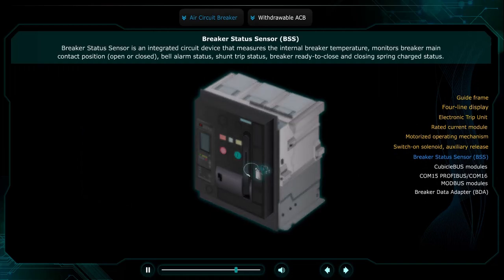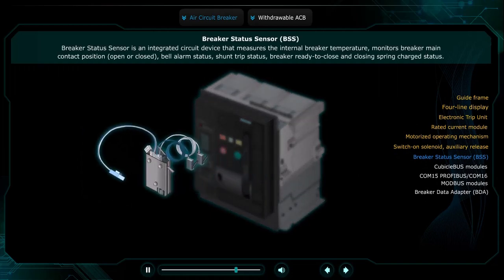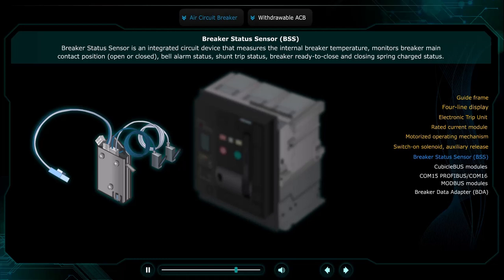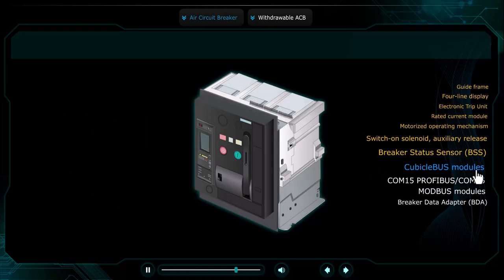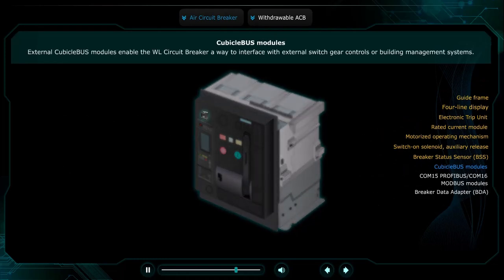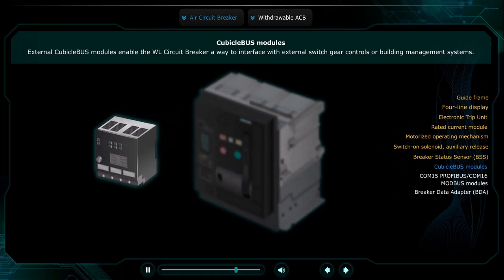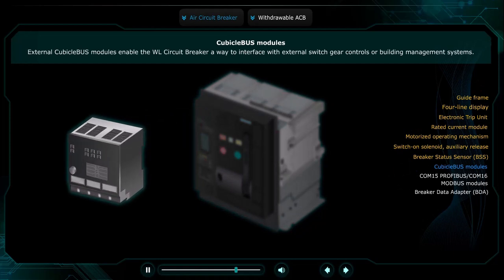Breaker status sensor is an integrated circuit device that measures the internal breaker temperature, monitors breaker main contact position, open or closed, bell alarm status, shunt trip status, breaker ready to close and closing spring charged status. External CubicleBUS modules enable the WL circuit breaker a way to interface with external switchgear controls or building management systems.